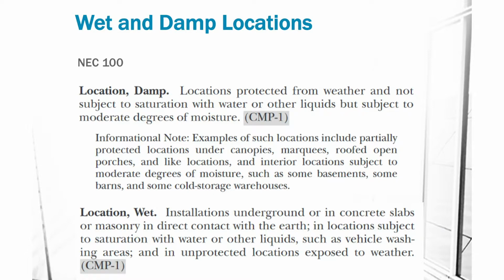Great. So moving on to a separate topic, the NEC defines what wet and damp locations are. Your wet location will be anything in slab on grade or below slab on grade, and conduits out to your light poles where you have security cameras on. Definitely your wet location. The damp location is if it's under an awning. So if it's outdoors but under an awning.